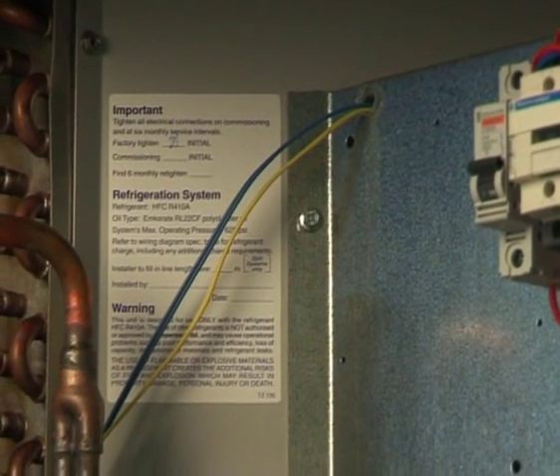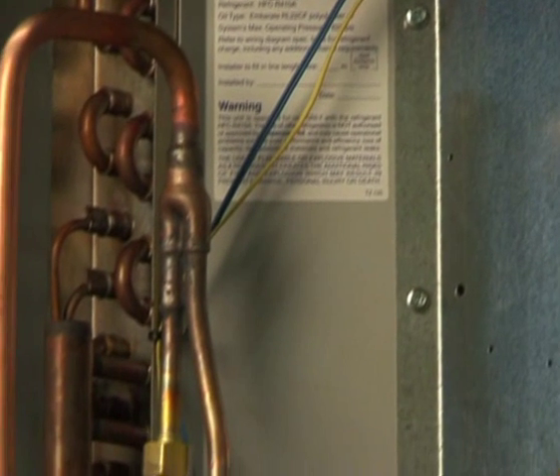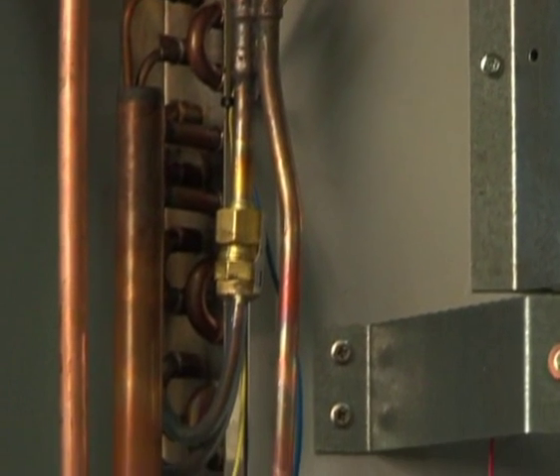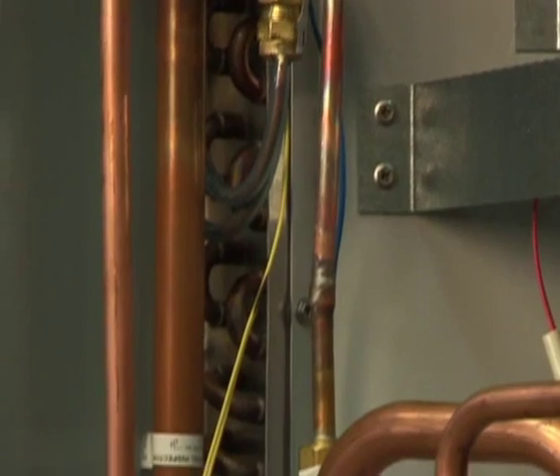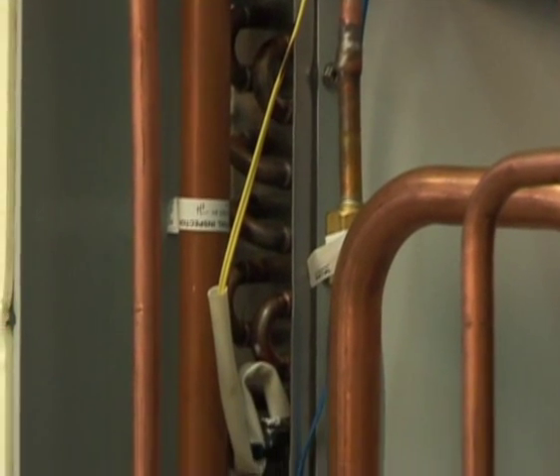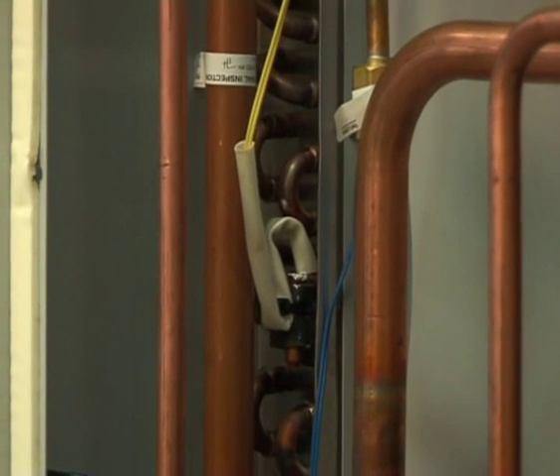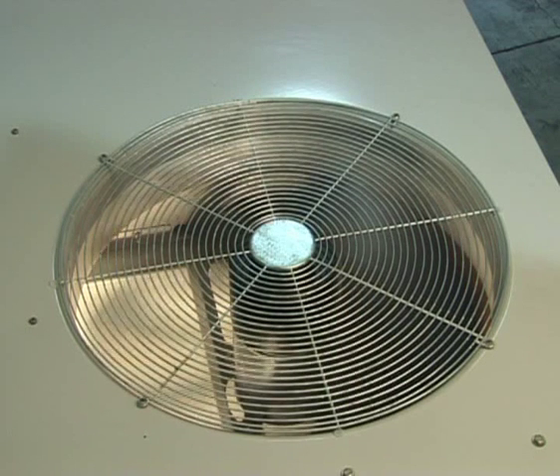The OUC also has built-in head pressure control to maintain a condensing temperature of 38 degrees C in the cooling cycle for R410A units. This feature allows the unit to perform at ambient temperatures lower than 20 degrees C without the risk of damaging the compressor. The condensing temperature is measured by the yellow sensor, which, as previously mentioned, is located in a pocket on a return bend of the condenser coil. Depending on the ambient temperature, the condenser fan speed is ramped up or down accordingly.